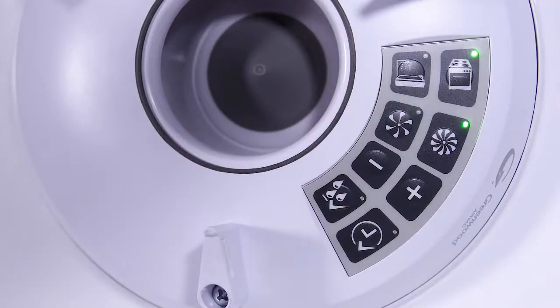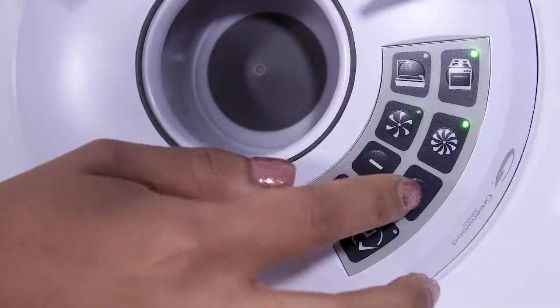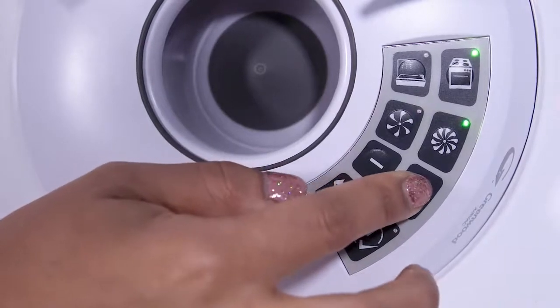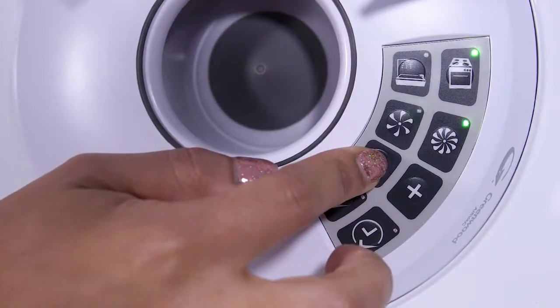This will automatically move you to set the trickle rate. As it's a continuous fan, the trickle will be permanently active. Set the trickle to your requirements. Note, you cannot have the trickle set higher than the boost.